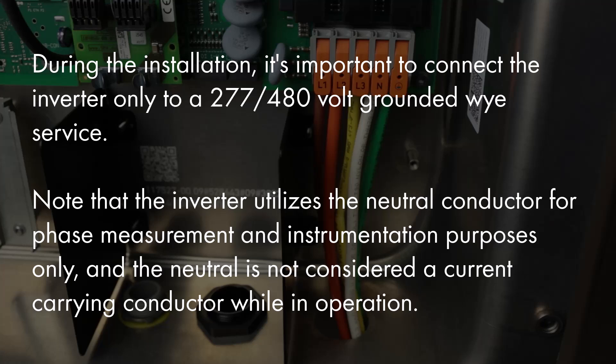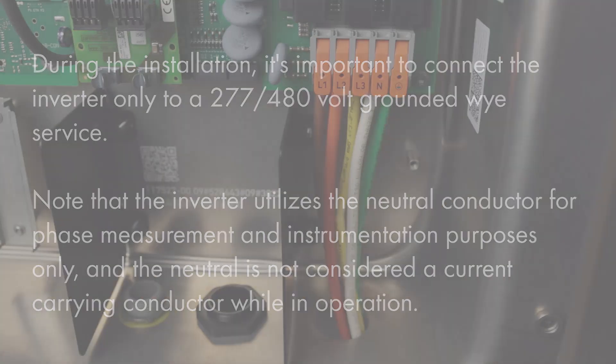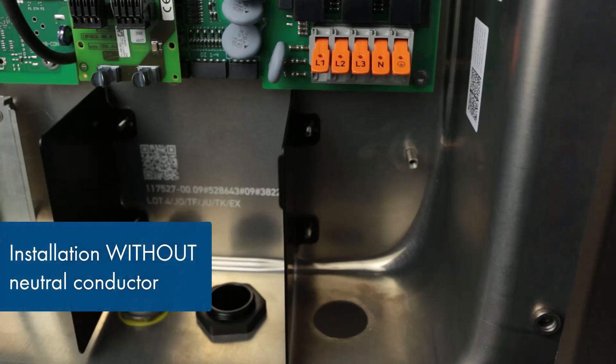During the installation, it's important to connect the inverter only to a 277, 480 volt grounded wye service. Note that the inverter utilizes the neutral conductor for phase measurement and instrumentation purposes only, and the neutral is not considered a current carrying conductor while in operation. If you choose not to use a neutral conductor, you must install the neutral ground jumper.